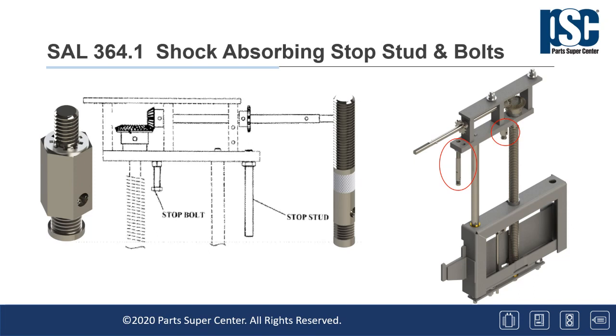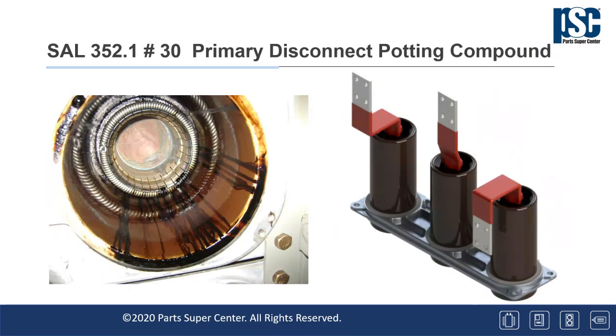The next recommendation is number 30 on SAL 352.1. This relates to the black pitch potting material in the tops of the primary disconnects. Primary disconnects are located in the switchgear. They are the interface point where the circuit breaker electrical bushings plug into the switchgear. You may hear them referred to by their slang names, bottles or jugs.